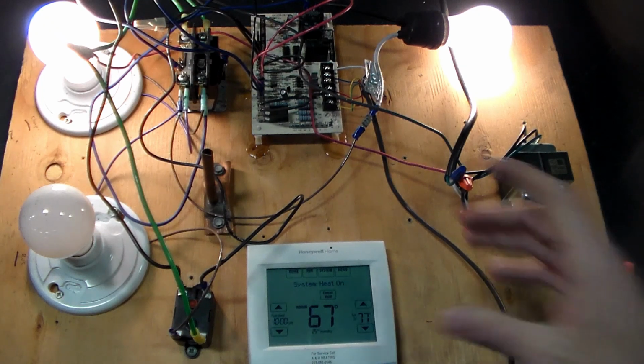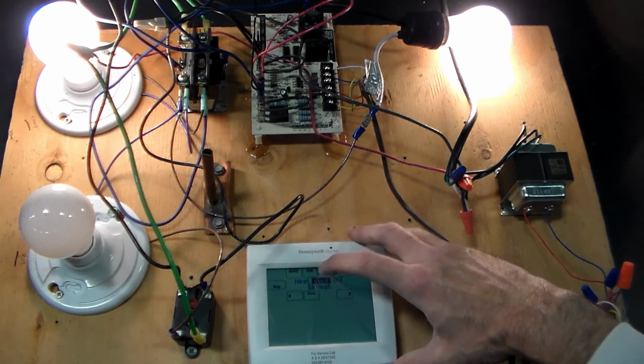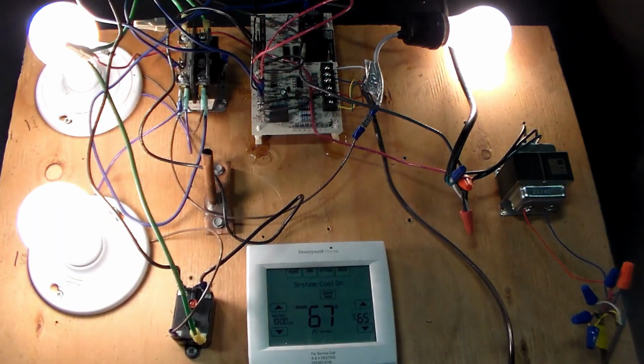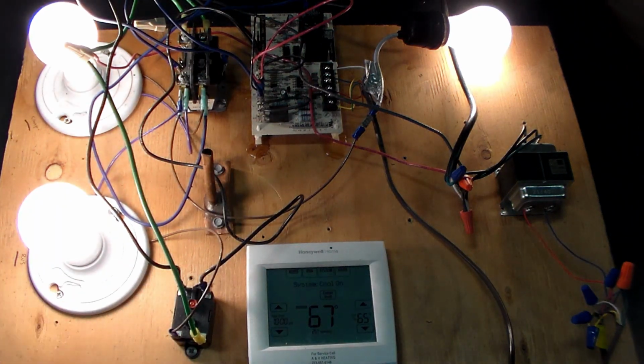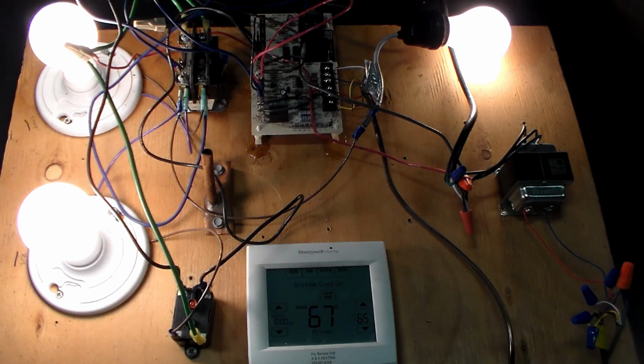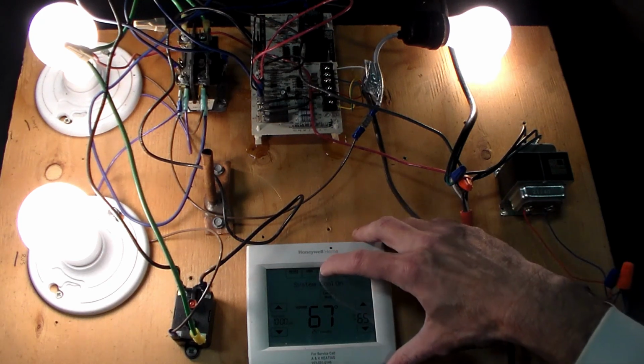And if I switch back to cool mode, hopefully it doesn't wig out my thermostat, then I re-energize my reversing valve. You're going to hear that whoosh noise. We're going to go into our call for cool. So let's put this back in heat.